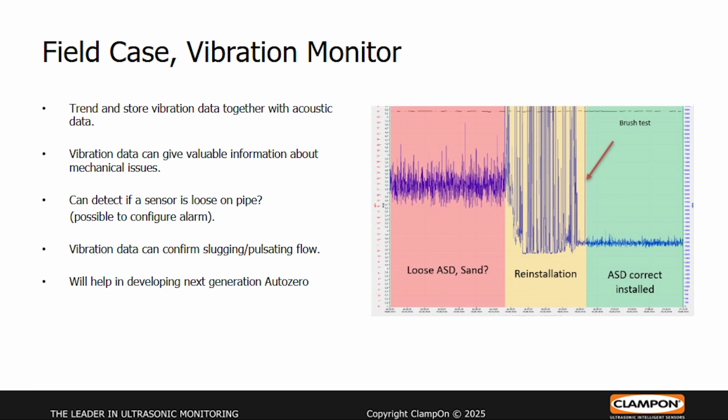In this trend here is an example of a sensor we discovered was loose. We reinstalled it here, and you see this is the acoustic level. But if you had the vibration monitored here, we would probably discover this.